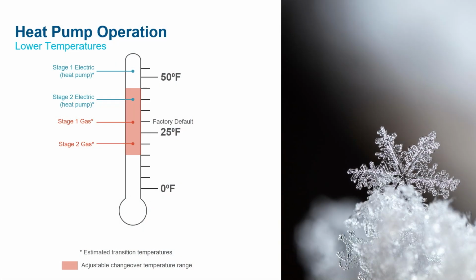Technological advancements allow heat pumps to work well below freezing outdoor temperatures. And dual fuel units, as discussed prior, can provide a hybrid approach, using the electric heat pump as a primary heating method with an auxiliary natural gas heater activated only on the coldest days. As shown in the light red, the changeover temperature range from heat pump to natural gas can be adjusted to occur between 15 and 45 degrees Fahrenheit, dependent upon the customer's goals for balancing comfort, payback, and emissions reduction.